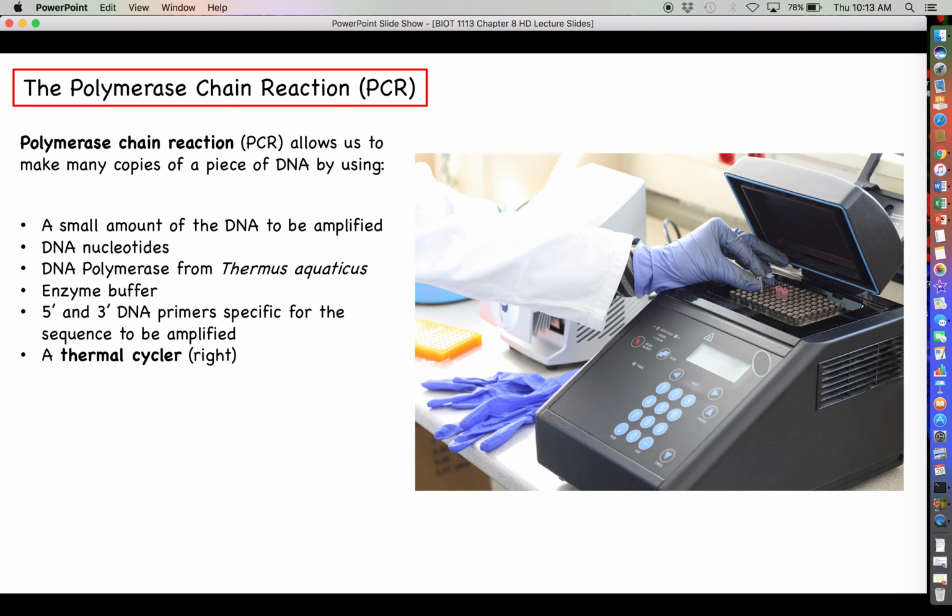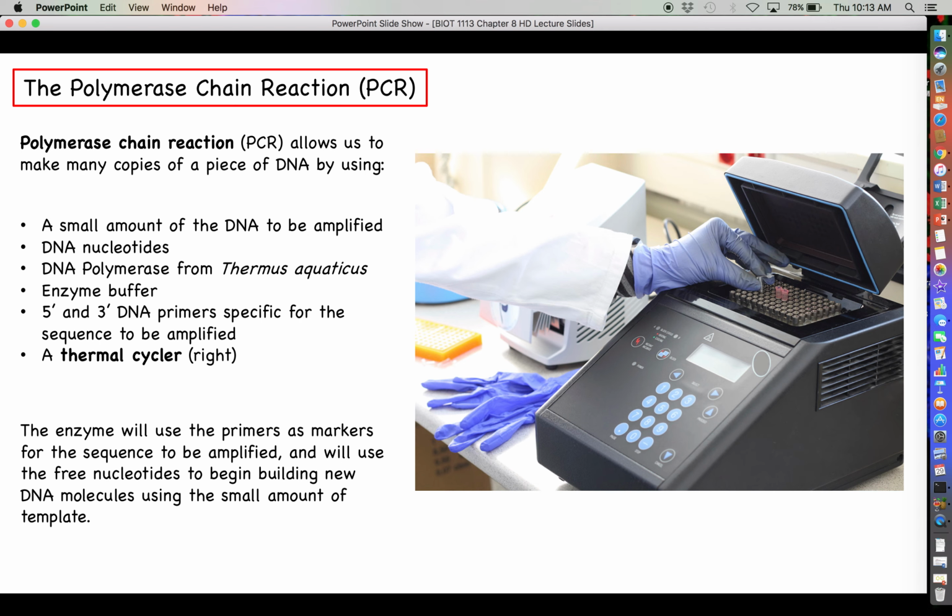So getting a PCR reaction to occur is really dependent on being able to go back and forth between those temperatures very, very quickly. So this machine here actually makes that very easy for us because this block right here that sits on top of the samples is a heat block that will rapidly change temperatures to get the temperature of the reactions to be exactly where they need to be.